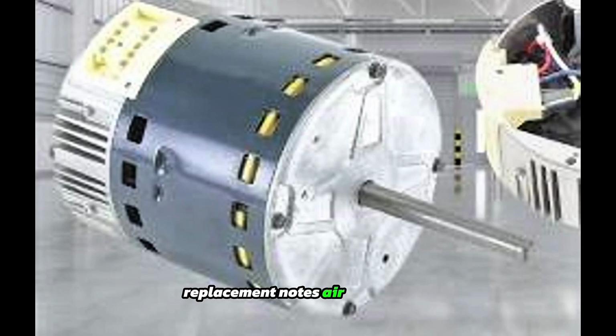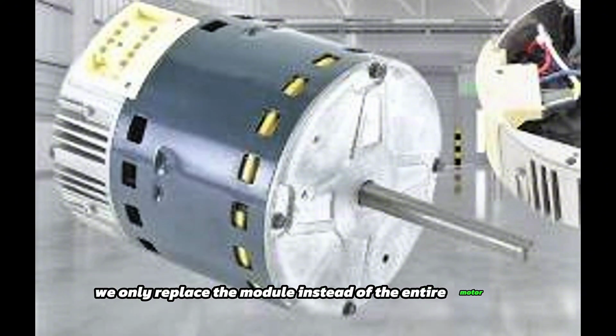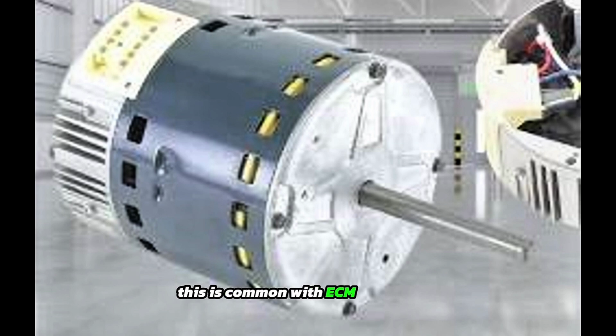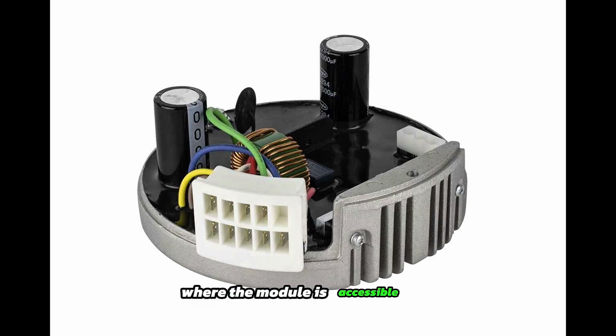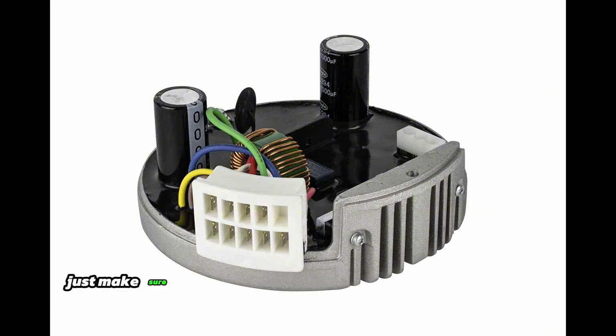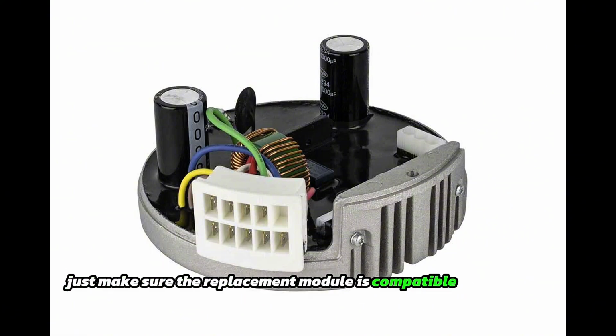Replacement notes: air handler. Sometimes, in residential air handlers, we only replace the module instead of the entire motor. This is common with ECM motors, where the module is accessible, and replacing it is easier and faster than removing the full motor assembly. Just make sure the replacement module is compatible with the motor model.